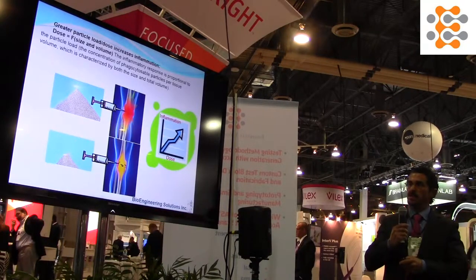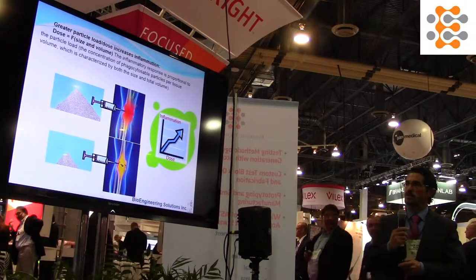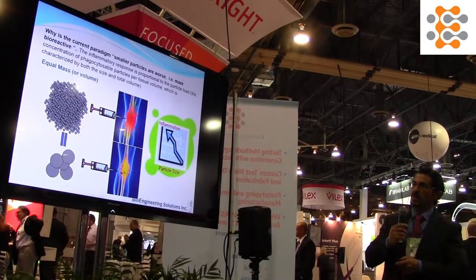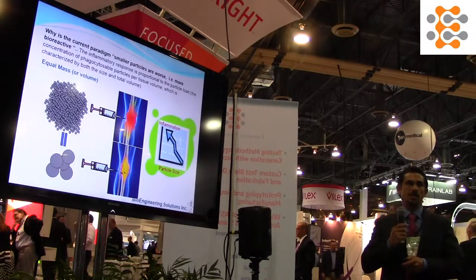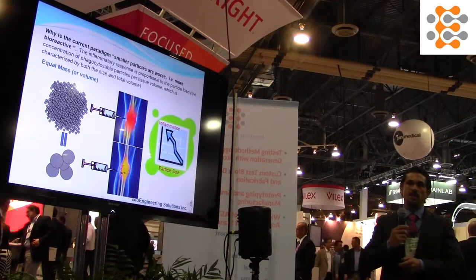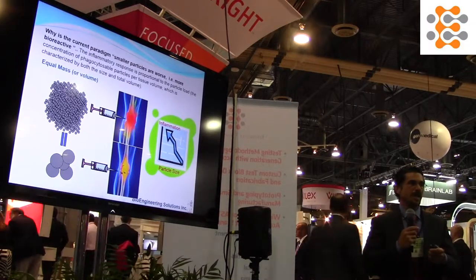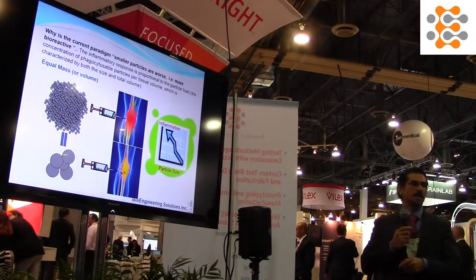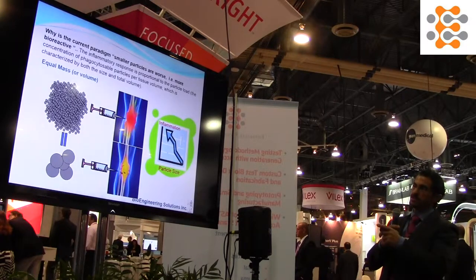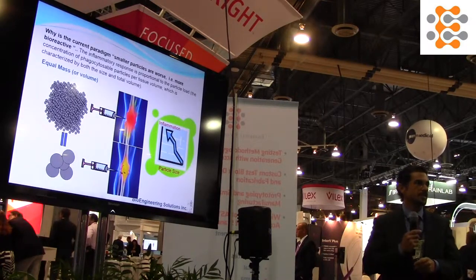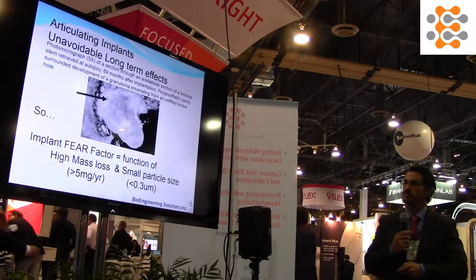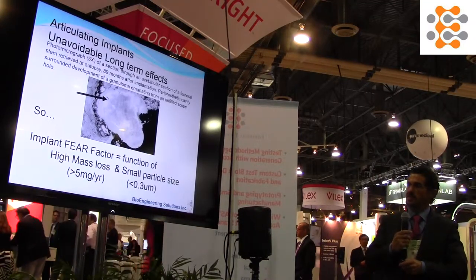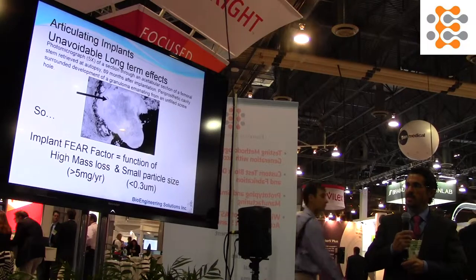There are some obvious things, like a greater dose of debris will create a bigger inflammatory response. But there are several less-known things: smaller particles are worse than large particles when judged from an implant gravimetric basis. If your implant loses 10 milligrams of wear debris as four large particles, that's not going to be a problem. But if it loses 100 trillion nanometer-sized particles, that's going to be more of a problem systemically and locally. So for articulating implants, the fear factor for companies is a high mass loss and small particle size.